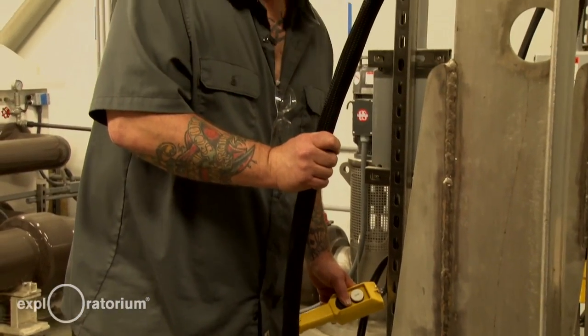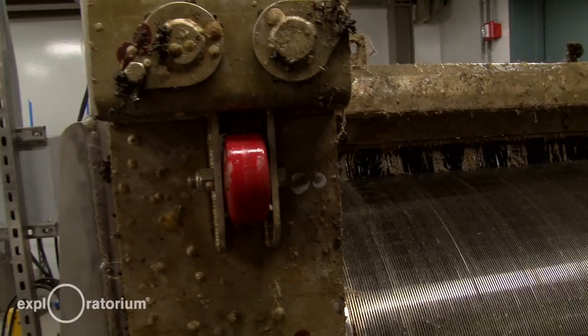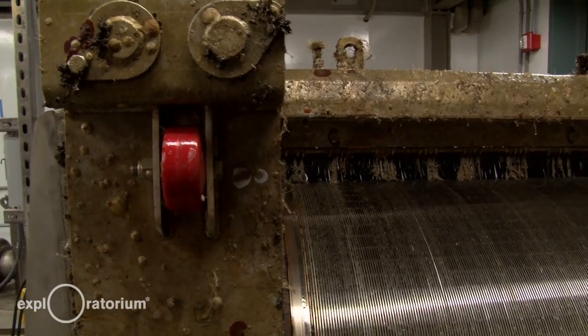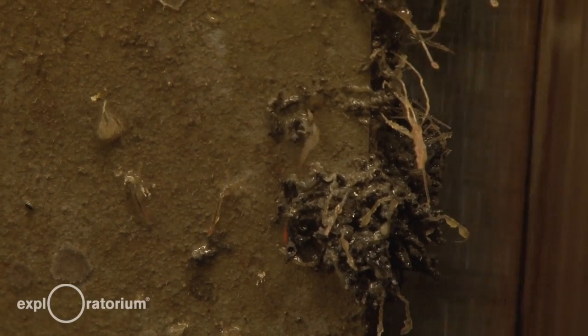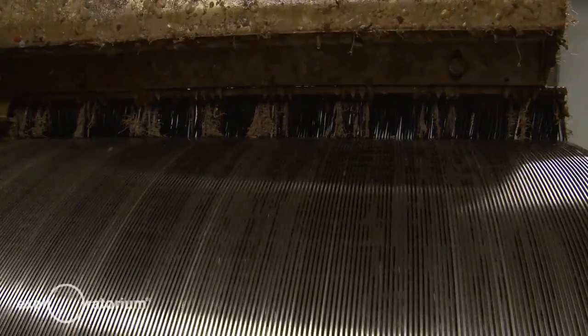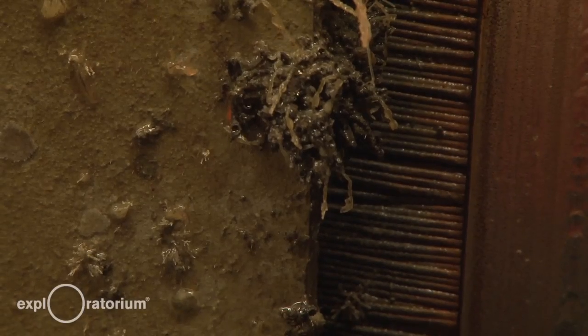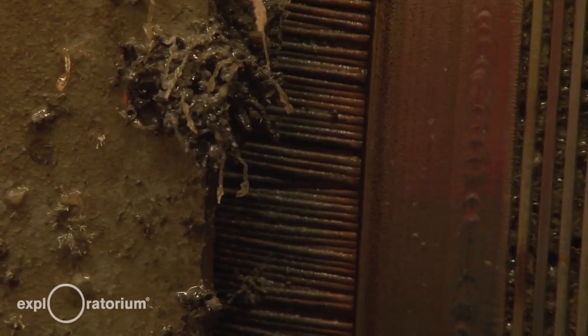This is the beginning of the filtration process of the seawater as it moves through this room to exchange the heat. This thing's only been in the water for a very short period of time — I think it was spotless two months ago — and it now has a lot of sea life on it. It's one of those things that has to come up about every two weeks and be scraped clean, or it will fester into this massive thing of sea life. The ocean water being drawn in creates a nutrient flow, so it makes for a perfect place for sea life to live.